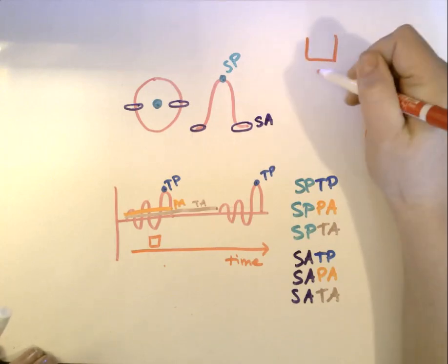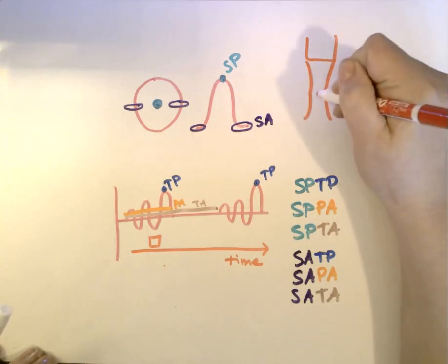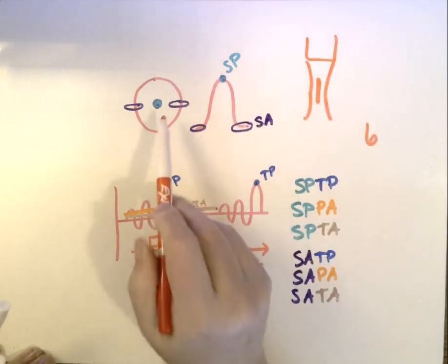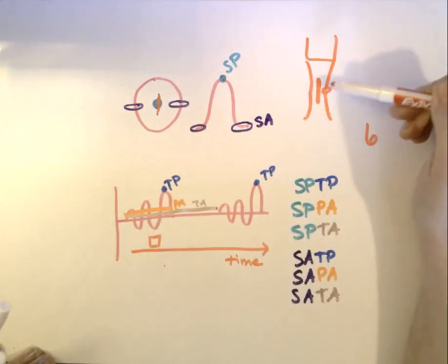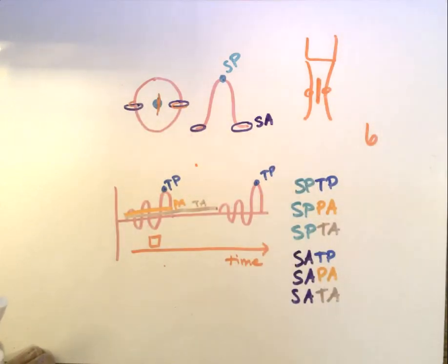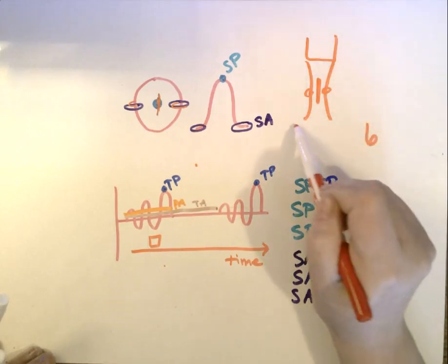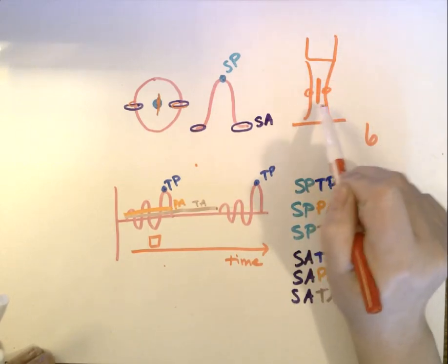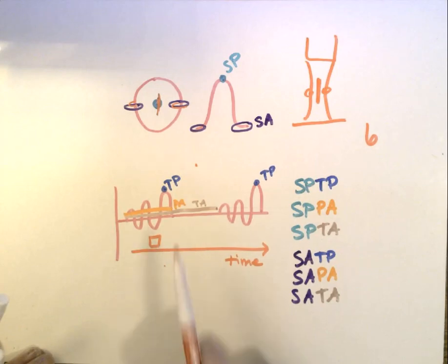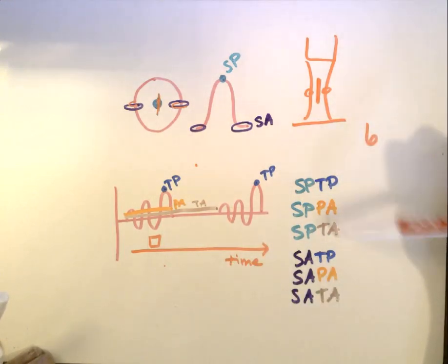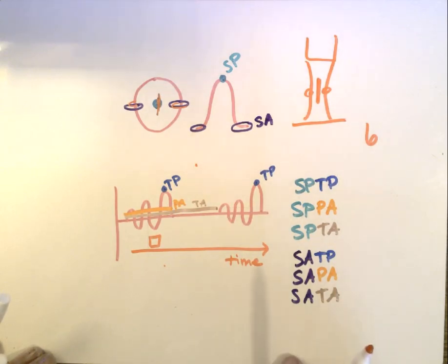The spatial part of the beam, so if we have our transducer and the beam is coming down like this, this area right here would represent this area here, where these edges are also these edges. So the very center of the beam is where that spatial peak is. The patient is always receiving the spatial peak and the spatial average, but they're not always receiving the temporal peak. We're averaging out the rest of the things that they are receiving. So it all just has to do with considerations of space and time.